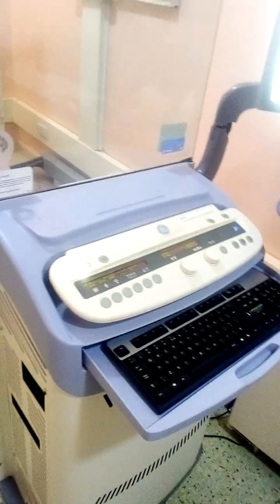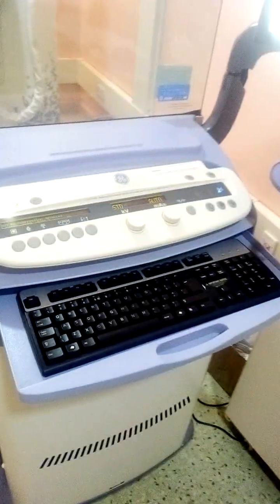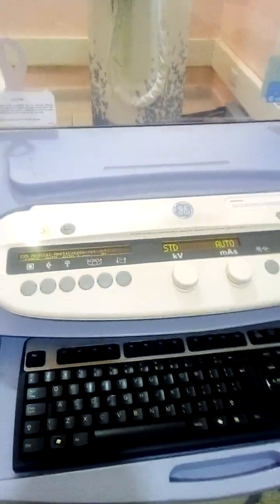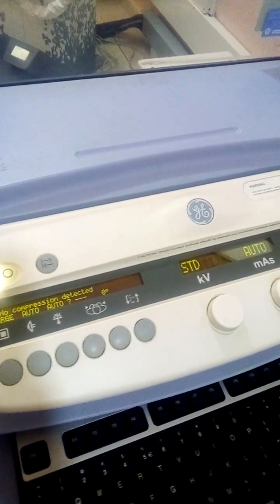Now when you come across here, we have the control panel. This control panel is also for setting the parameters that you want to use for taking the images or scanning. As you can see now, we have the kV setting, we have the mAs, and these values you set depending on the penetration of the phase that you want to get the image from. This is the screen that shows what you have set.